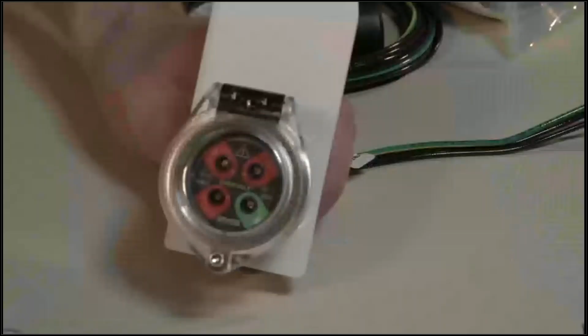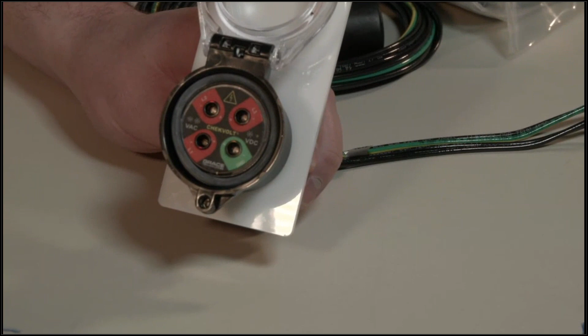So the newest product that we wanted to talk to you all about today is our check volt. The check volt solution, it may look familiar, but it actually combines our dual redundant LEDs from our voltage indicator with our contact tester safe test point device. The great thing about this solution is it's all in one easy to use product. It meets the standard within NFPA 70E, no exceptions. So the check volt mitigates arc flash and shock hazard, and it enhances your compliance to NFPA 70E.